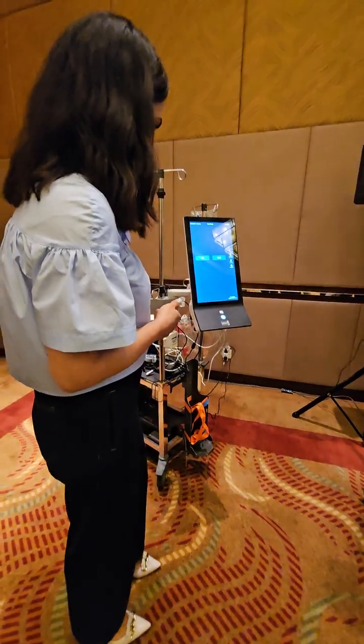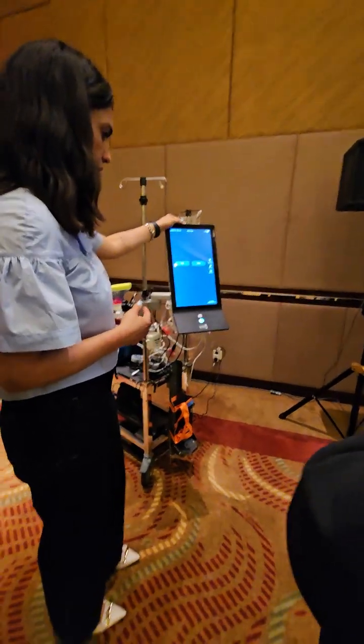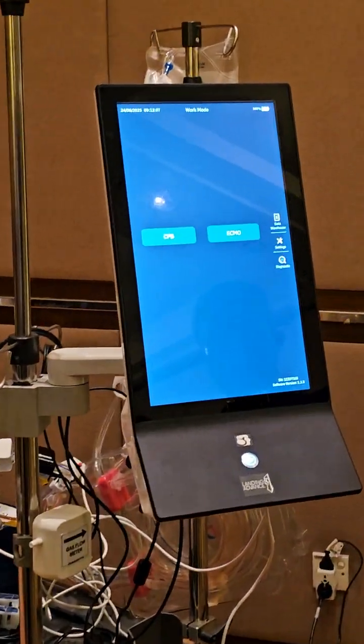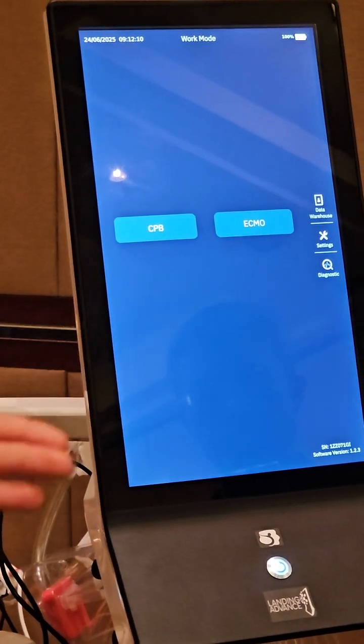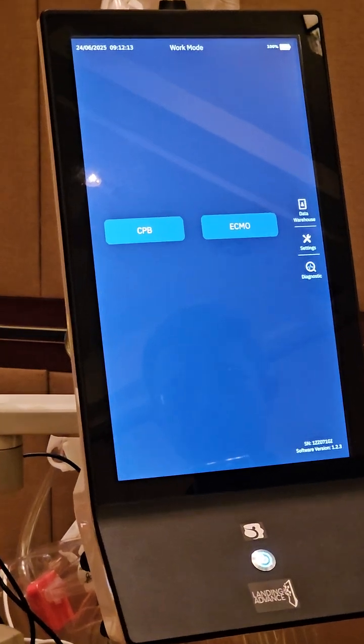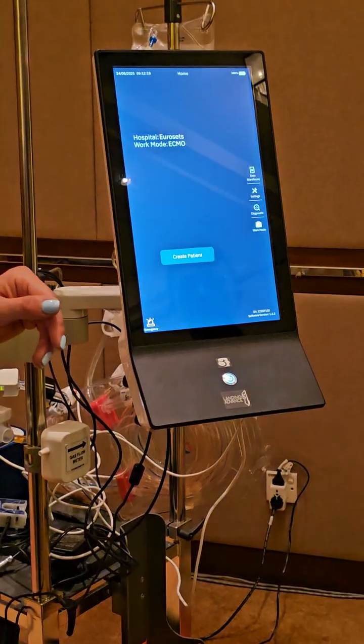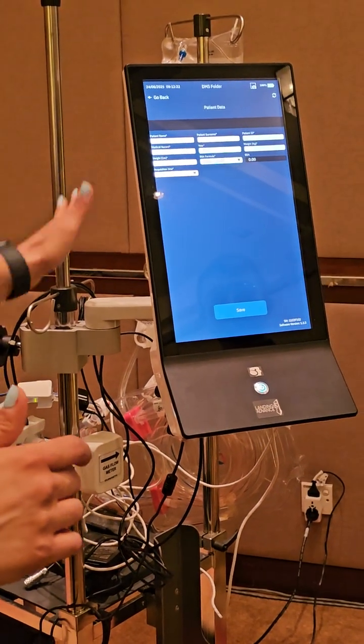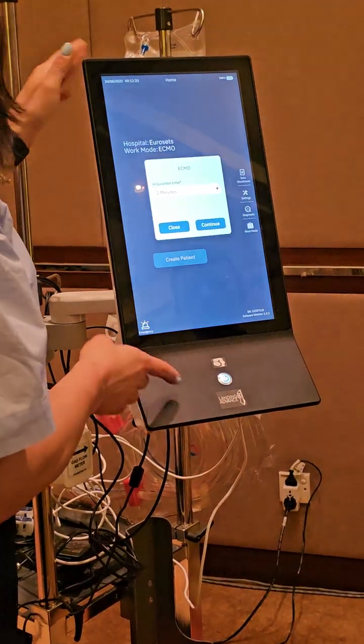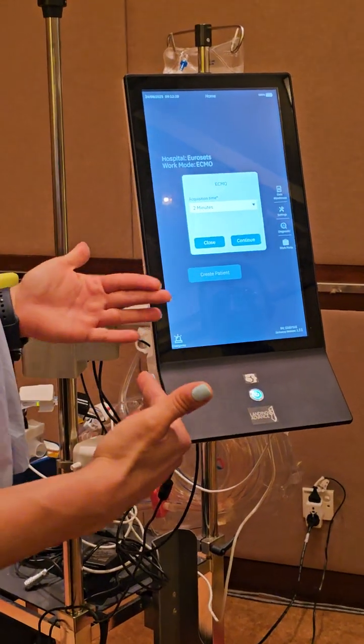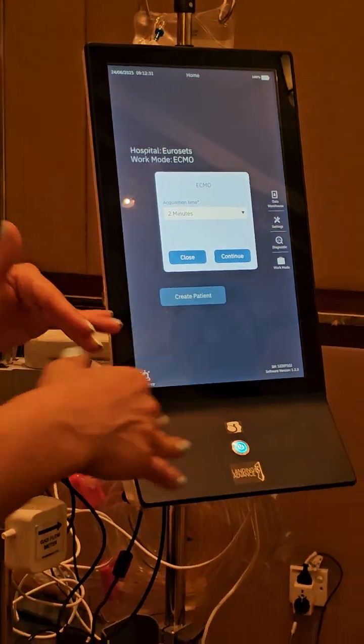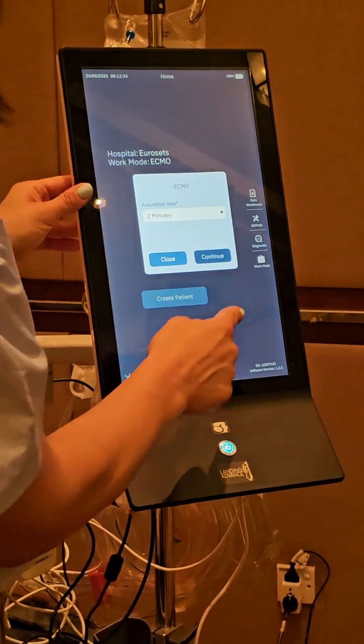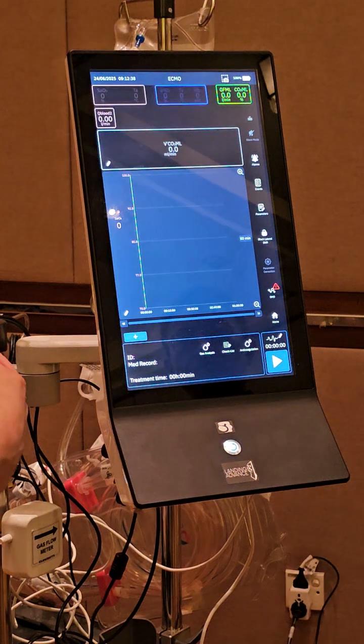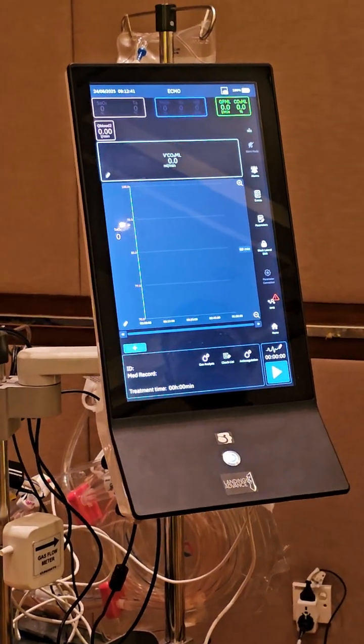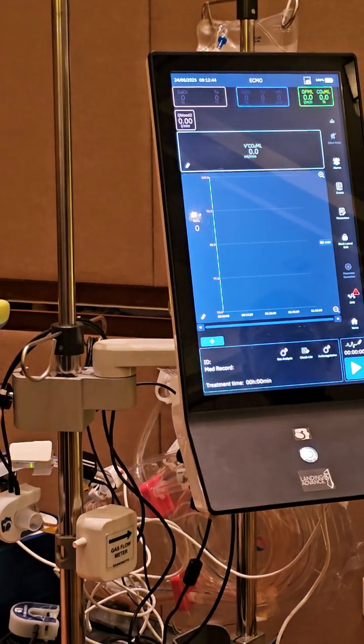So once you pass the diagnostic phase, the first thing that you have to choose is the work mode. As we said, Landing Advance is able to be used and is validated both for CPB and ECMO. So once you pass the diagnostic, you can choose between CPB and ECMO. You choose ECMO. We create our patient, so some data are mandatory, but in case you have no time, you can also skip this phase, and it is really appreciated because when you are in emergency, you have to be as fast as possible. And you continue. When you continue, you enter directly in the treatment page, in the ECMO work mode.